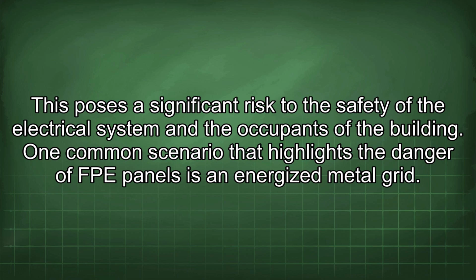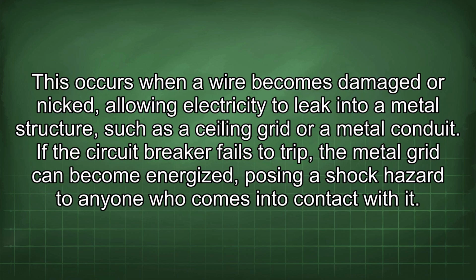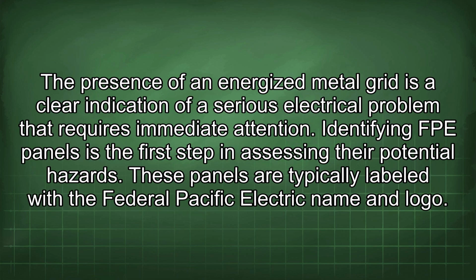One common scenario that highlights the danger of FPE panels is an energized metal grid. This occurs when a wire becomes damaged or nicked, allowing electricity to leak into a metal structure such as a ceiling grid or a metal conduit. If the circuit breaker fails to trip, the metal grid can become energized, posing a shock hazard to anyone who comes into contact with it. The presence of an energized metal grid is a clear indication of a serious electrical problem that requires immediate attention.